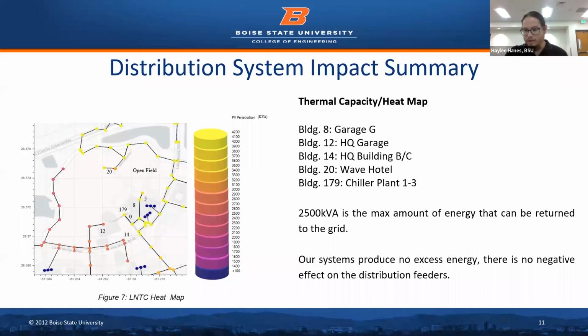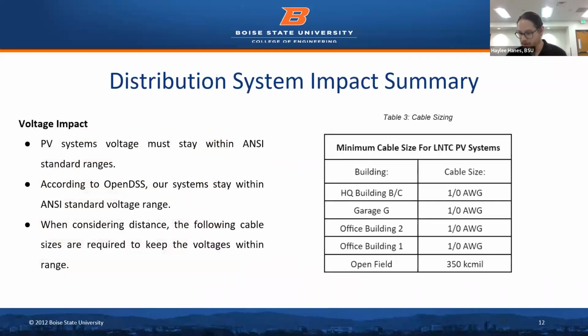However, when considering distance, the voltage goes out of range, so we used a cable and voltage drop calculator to find the minimum cable size needed for our systems. As you can see, most of our buildings require 0 gauge cable sizing, except for the open field, which when connected to the Wave Hotel requires a cable size of 350 kcmil.